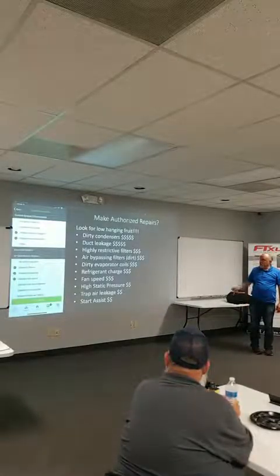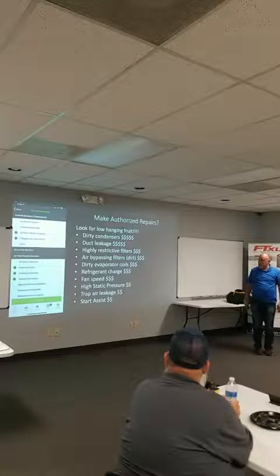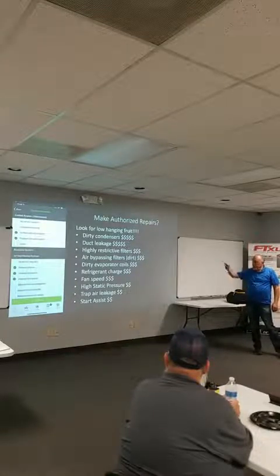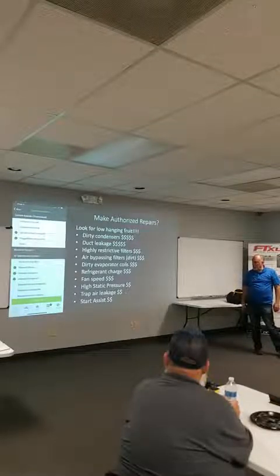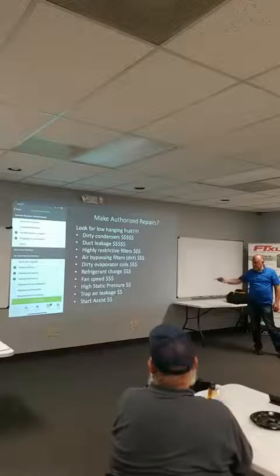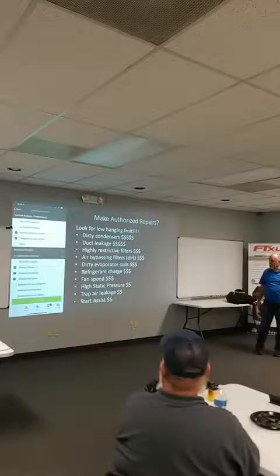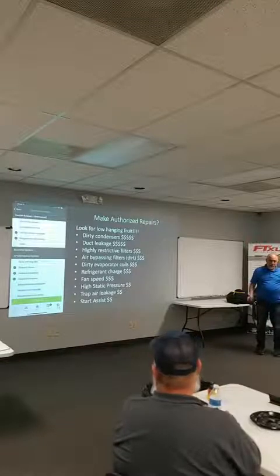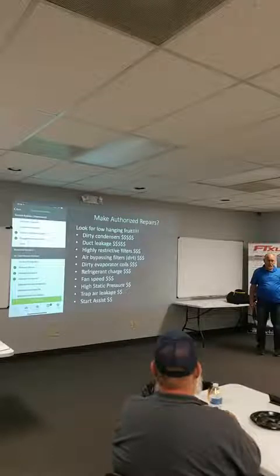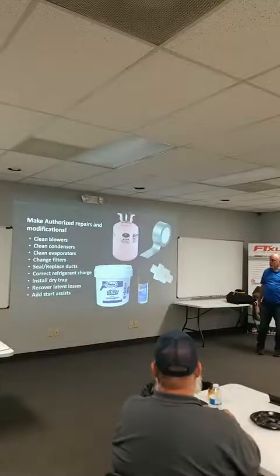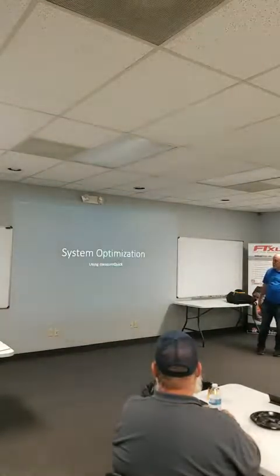So the quick fixes here, the most low-hanging fruit in our industry: dirty condensers, duct leakage, highly restricted filters, air bypassing the filters leading to dirty evaporator coils, refrigerant charge, fan speeds, high statics, and trap air leakage, another big problem we have. You see this a lot on rooftops where you've got a draw-through system and your traps are not big enough. They're using an undersized trap. You're just pulling air through there, or you're not draining the water and you're re-evaporating the water back into the space, right? A lot of these things aren't big expense.